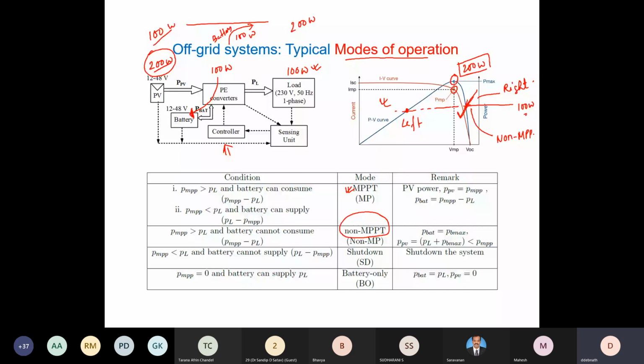Another case may appear when solar power is very less and load demand is high, but battery is already discharged, so battery also cannot supply your load demand. So you have to shut down your system, or maybe serve only critical load for the time being. There can be another mode when solar power is totally zero during night time and battery is supplying the load demand. So this is actually a subset of this.